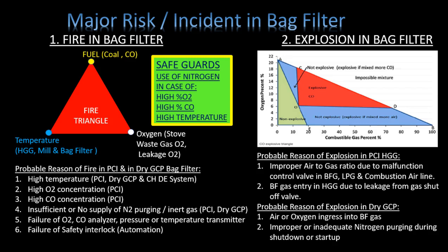Safety measures in PCI bag filter include inlet temperature control and nitrogen purging in case of high temperature, high oxygen percentage, or high carbon monoxide gas concentration. In dry GCP, due to very high furnace top temperature the bag filter bags could be burned. Safety measures include furnace top temperature control by opening the top water spray and nitrogen purging in dry GCP inlet and individual silos.